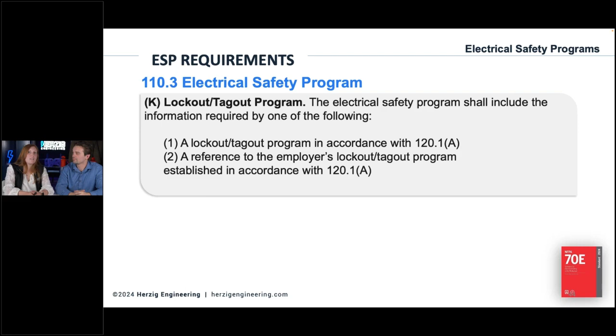Well, all electrical conductors or circuit parts shall be considered energized until verified to be de-energized through the process of achieving an electrically safe work condition. Yeah. Simply put, there's more steps. Okay, it's not a standard lockout, tagout thing. If you're going to be exposed to those conductors or circuit parts, you have to do what James just said. Yep. Either act like it's still energized, or you complete the process of achieving an electrically safe work condition. Yeah. These steps do need to be fleshed out, explained, detailed in your safety program. This is very important. Yeah.